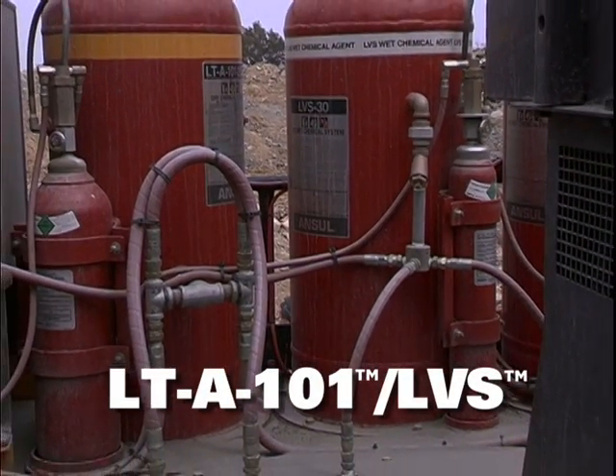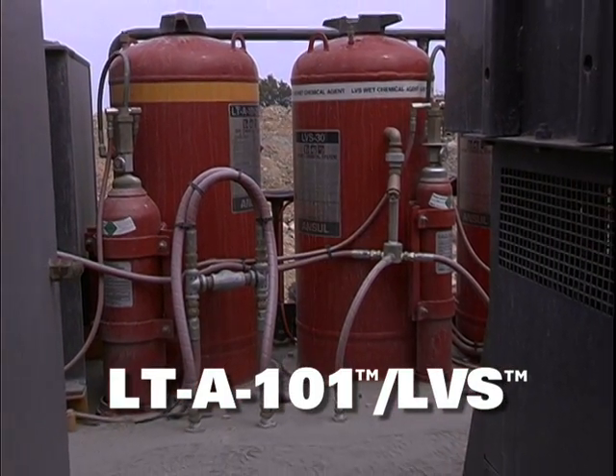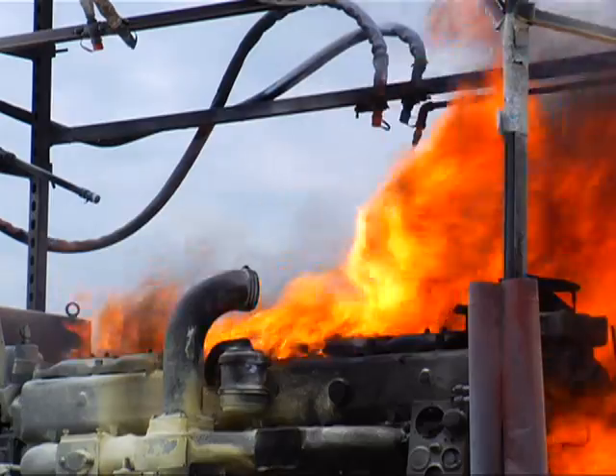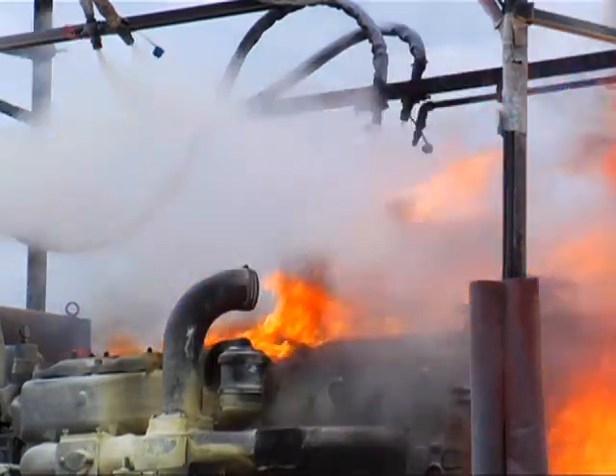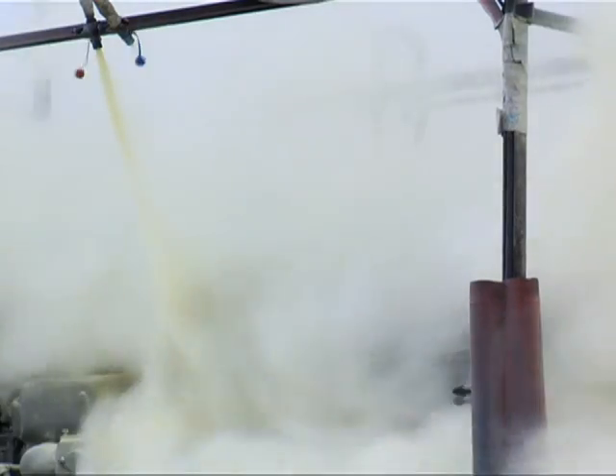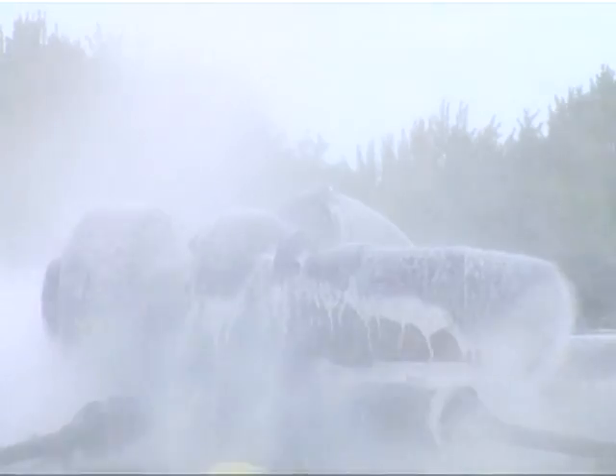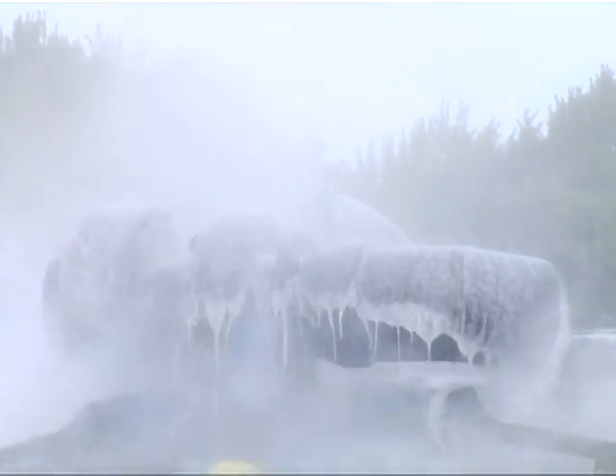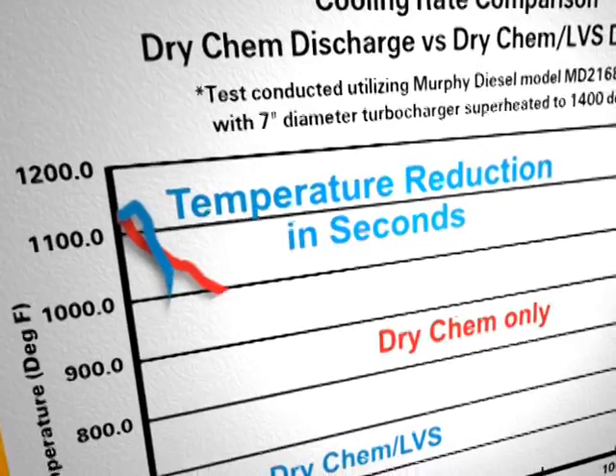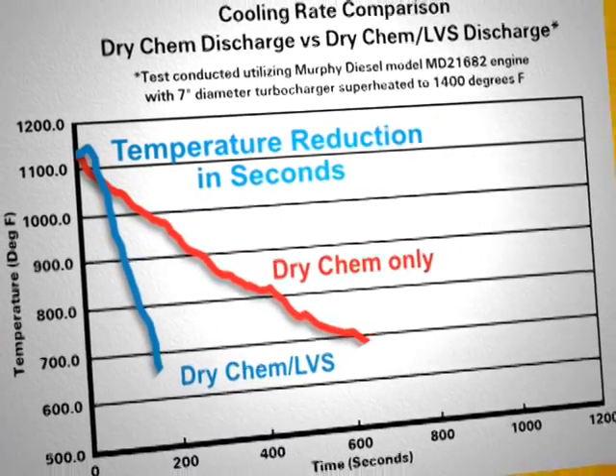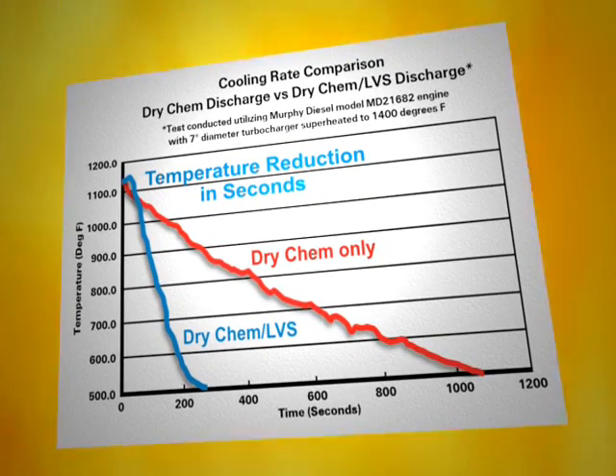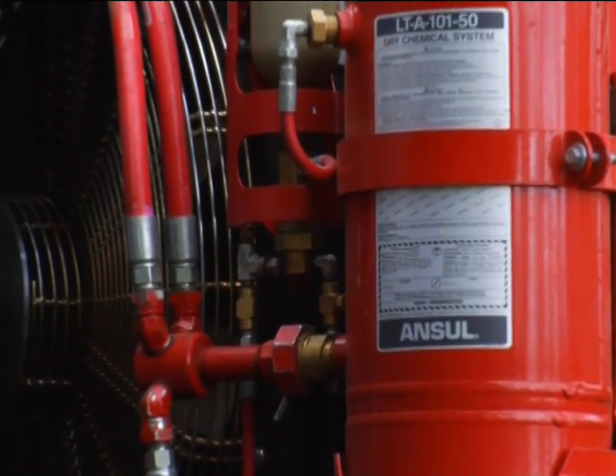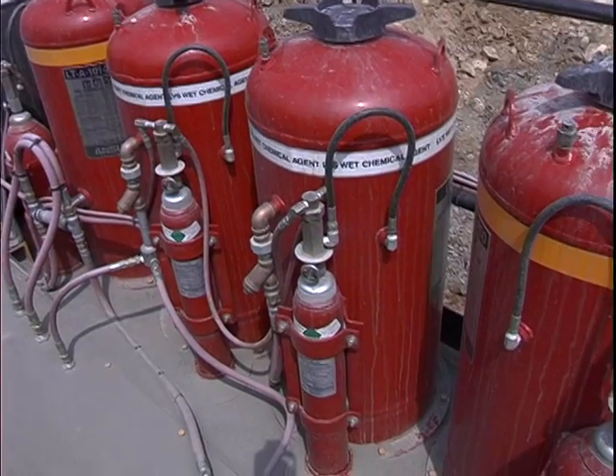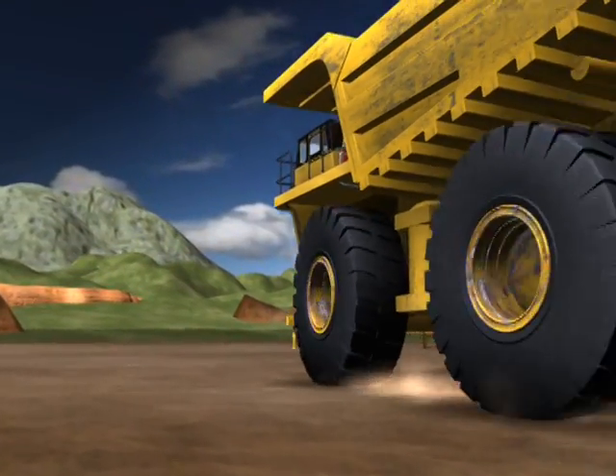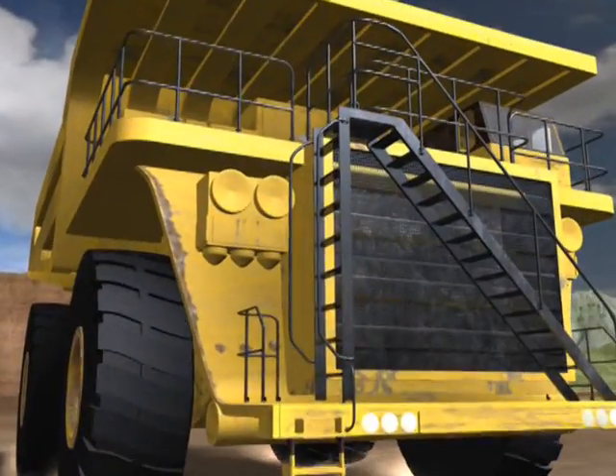For the ultimate in protection, install the LTA-101 LVS twin agent system. When actuated, the system discharges both 4A dry chemical and LVS liquid agents simultaneously. This combination is fast and effective, suppressing the flames of a fire and cooling the hazard area to help prevent fire reflash. This graph illustrates the effectiveness of the Ansul LTA-101 LVS twin agent system versus a single dry chemical system. Either system you choose, whether dry chemical only or twin agent with LVS, you'll find quality fire protection for your equipment. Now, let's take a look at how the LTA-101 LVS system works in an emergency situation.